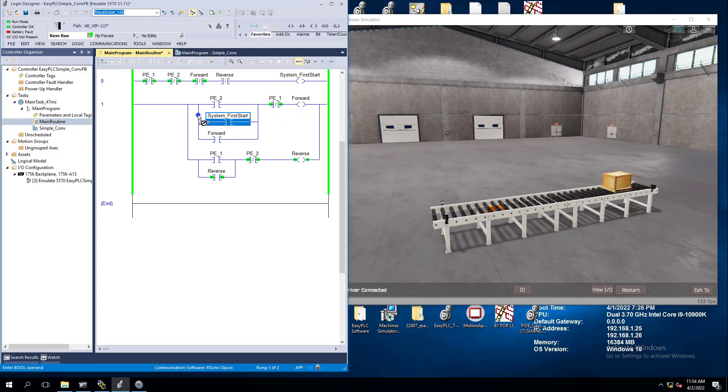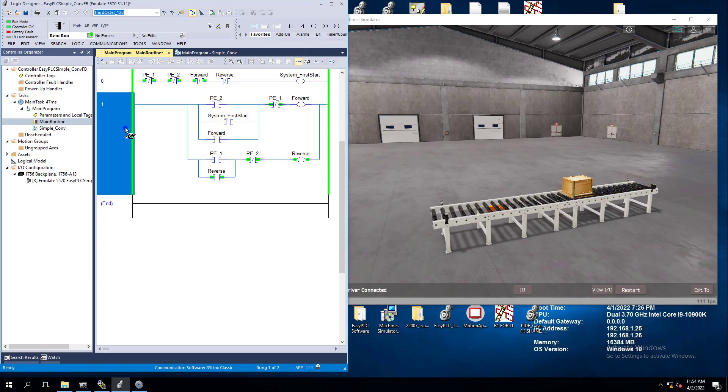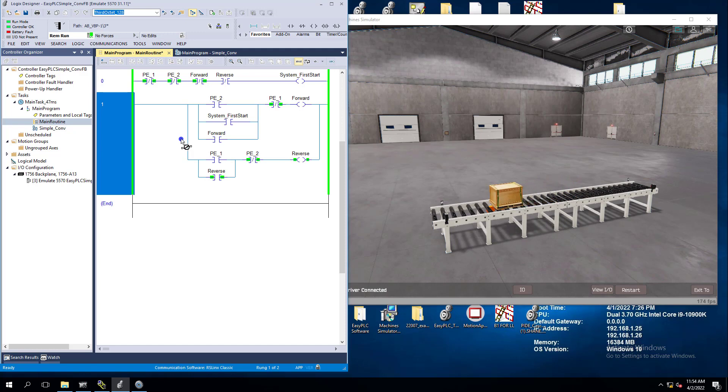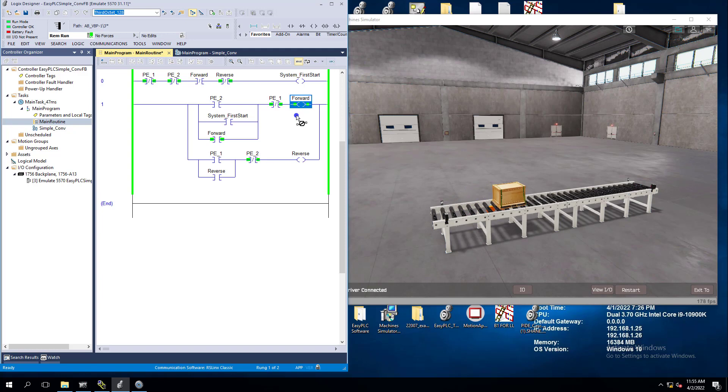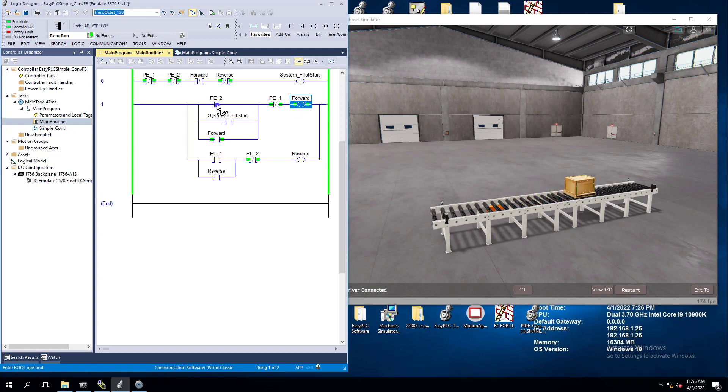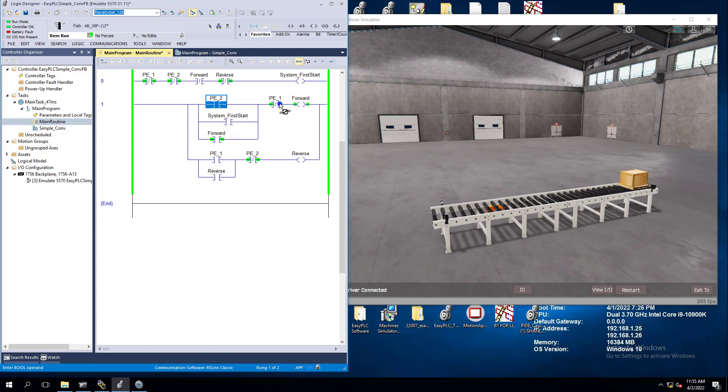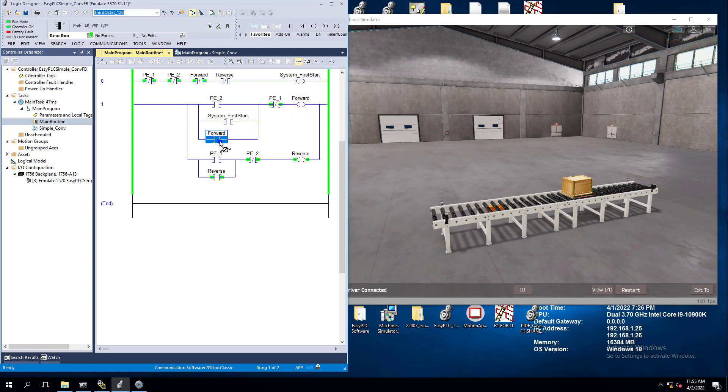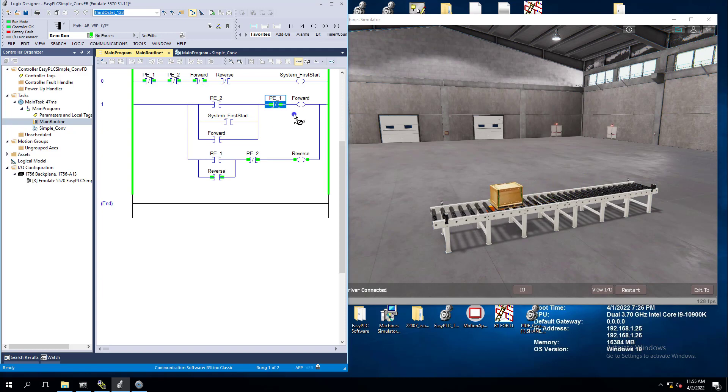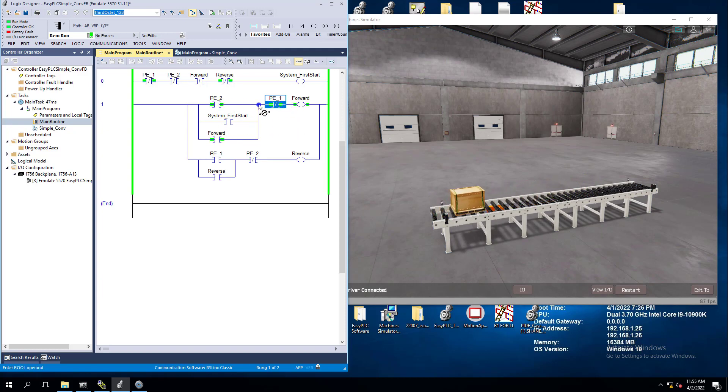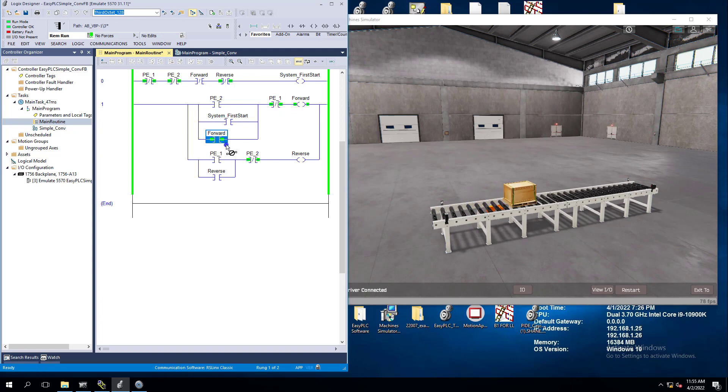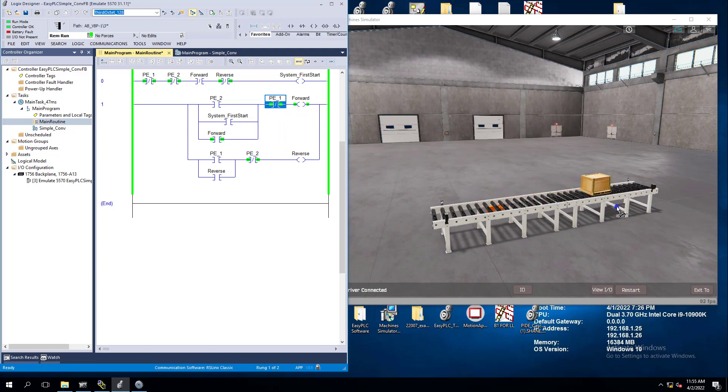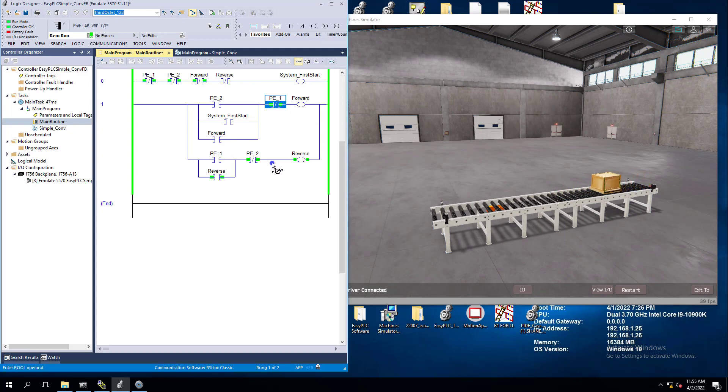You can see that latching in basically forward. Now I'm still using a logical latch, not a latch boolean or unlatch. I'm using a logical latch, which is a logical latch saying if photo eye 2 is made and photo eye 1 is not made, turn on the forward and latch it in until photo eye 1 is made then unlatch forward. Which will happen right now. You see that? It latches in the forward command until photo eye 1 right here is made. When photo eye 1 gets made, it unlatches and latches in the reverse command.